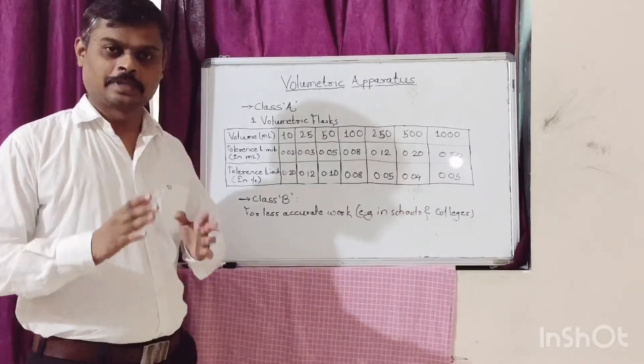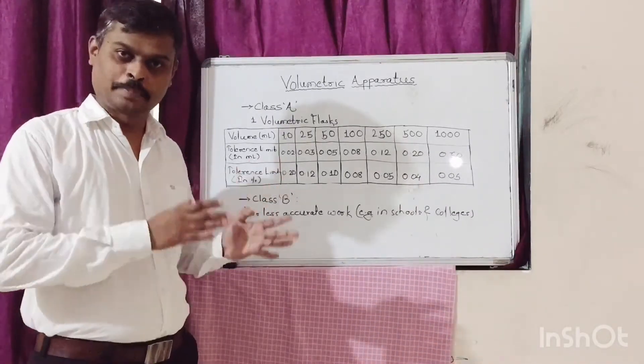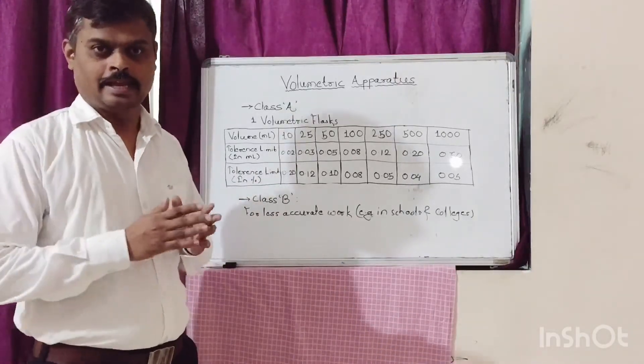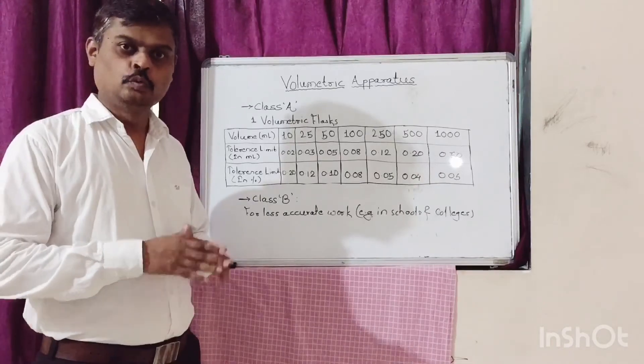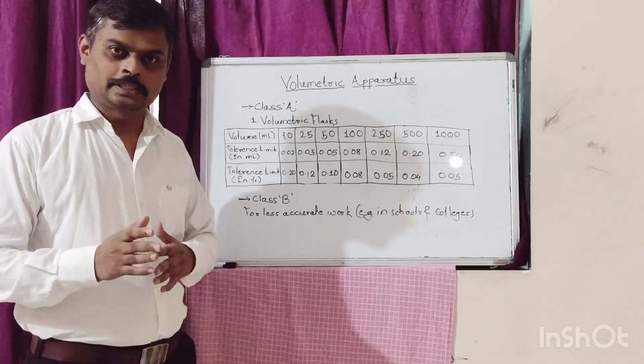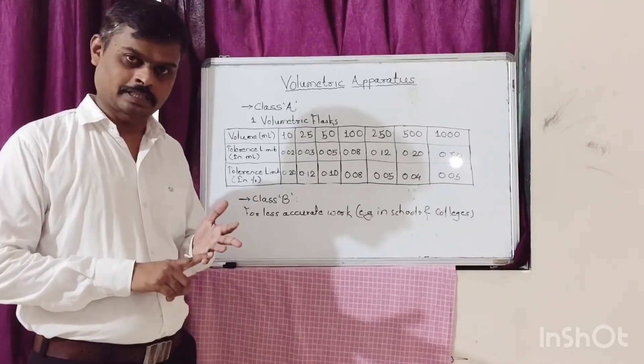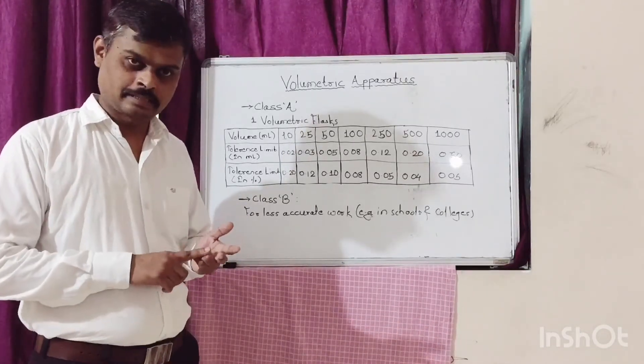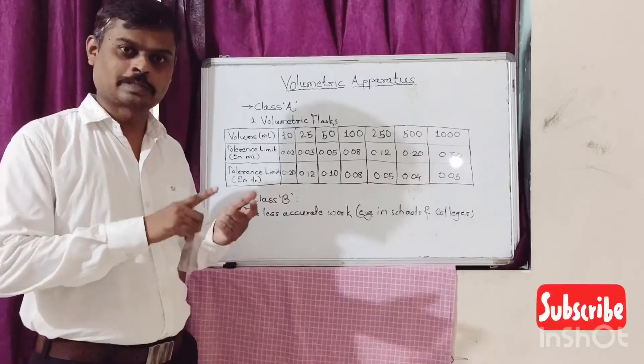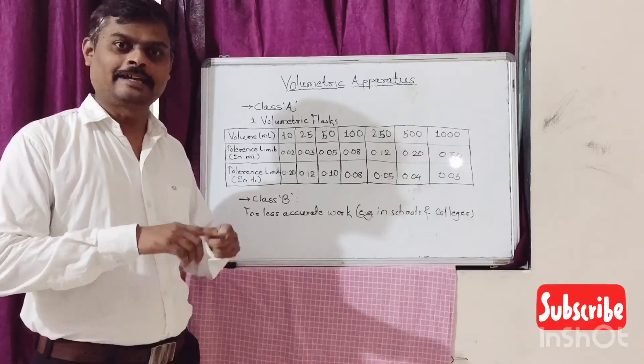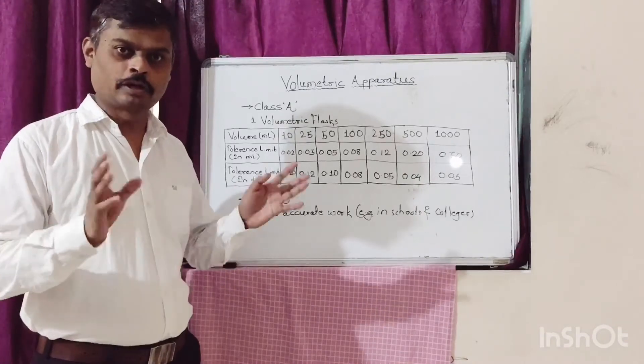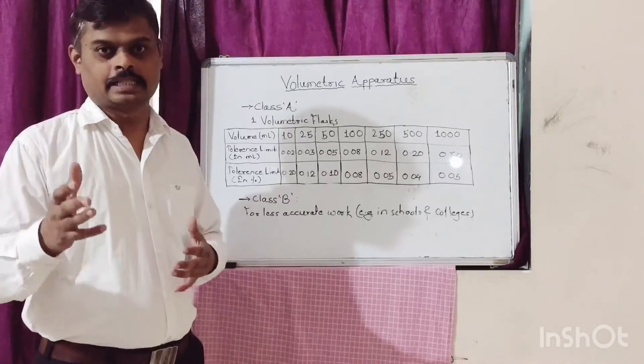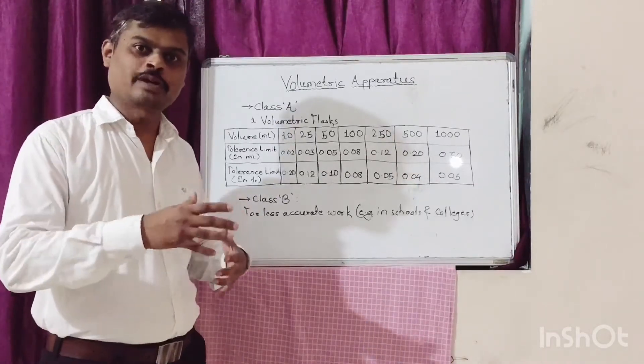Glassware calibrations are generally done at temperatures between 20 to 25 degrees Celsius. Hence, it is recommended to minimize volumetric error by ensuring that the volumetric apparatus used for analysis, the material to be analyzed, the solvents and diluents, and the laboratory environment are all maintained between 20 to 25 degrees Celsius to get more accurate results.